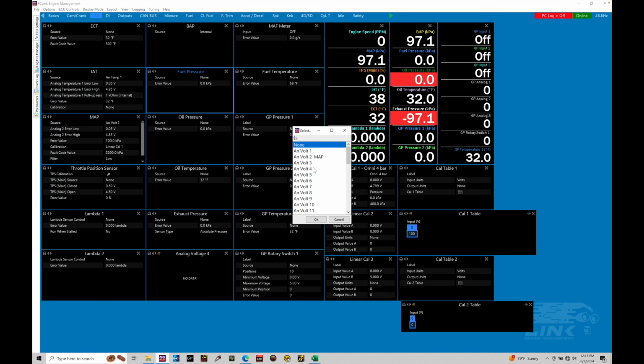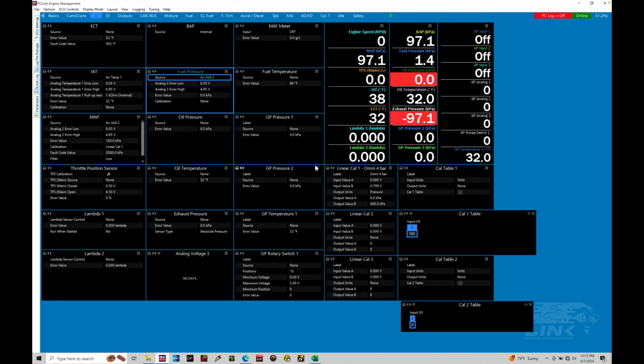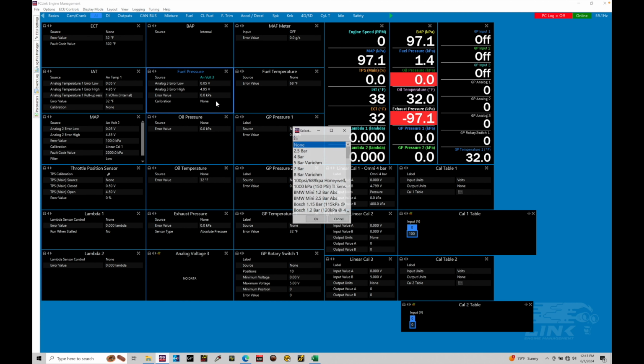So in this case, I'll go ahead and set this up on analog voltage 3. Now, low and high error, we have to program error value. If it faults above or below, that's what it's going to default to, and then we have to set up our calibration information. Now, in our calibration information, in our dropdown, we can find here that I do have a 100 psi sensor. I could choose this option, but I want to make sure that I have the scaling correct for the AEM sensor. We'll find that this is applying to a Honeywell sensor.